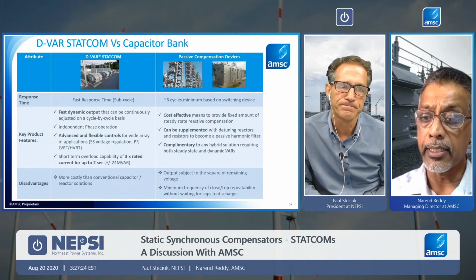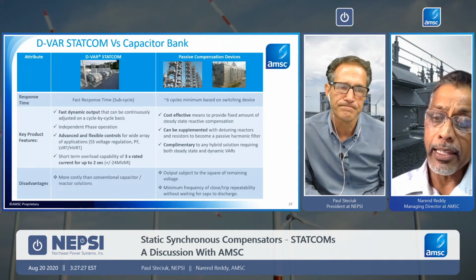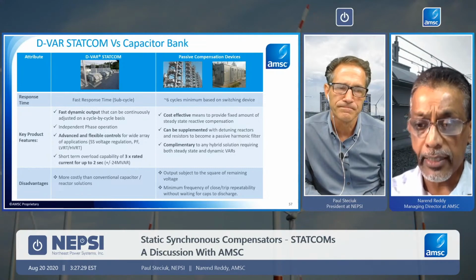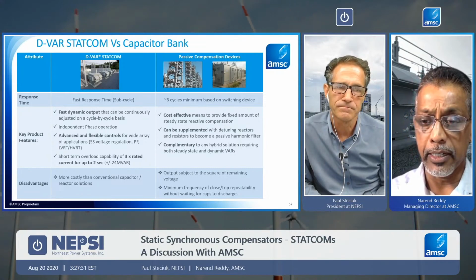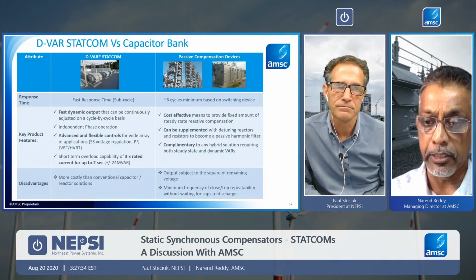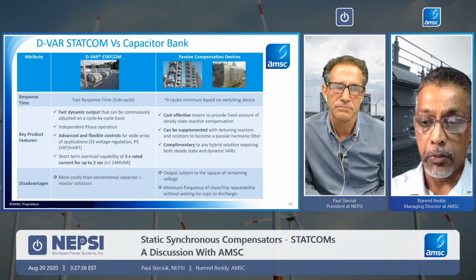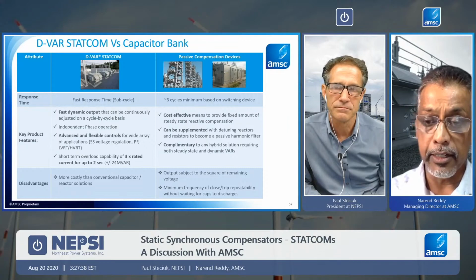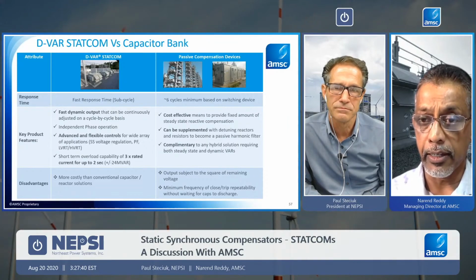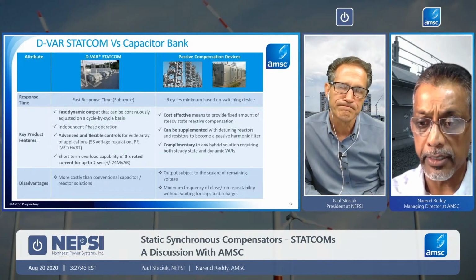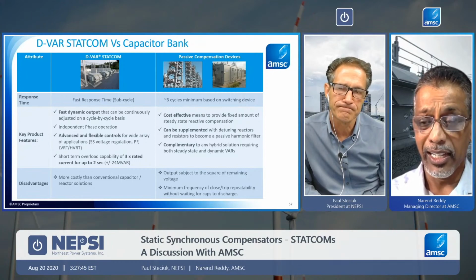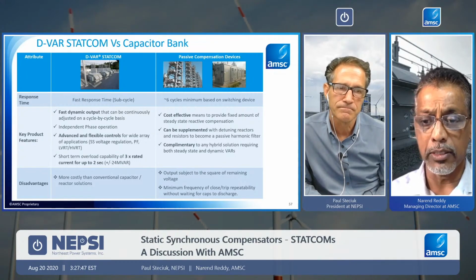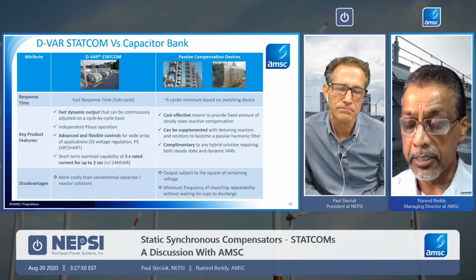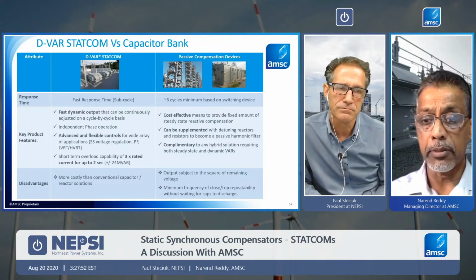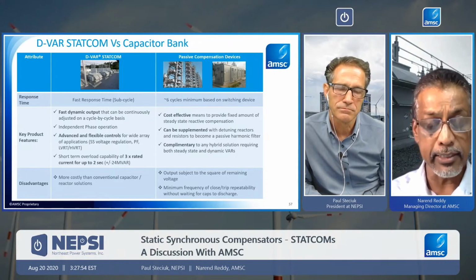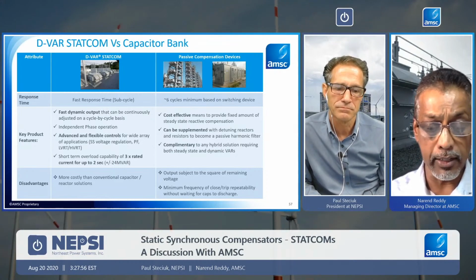But in some cases where you may have need for capacitive as well as inductive capability at one point, and the application would be such that you need both. Well, now you may want to consider a STATCOM, because if you go putting in a couple of cap banks plus a couple of reactors, and if you consider all the switches, the footprint, and all of that that goes with installing that, maybe just one STATCOM unit would be able to handle both of that. So there are some ways that you could look at both of them.